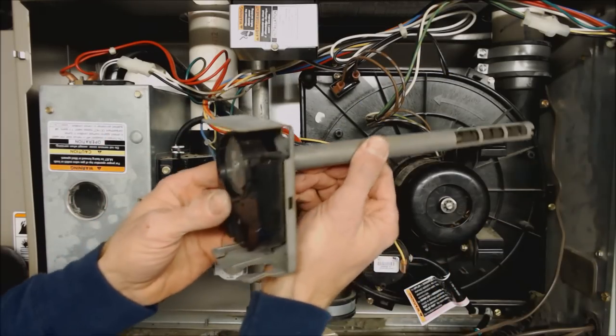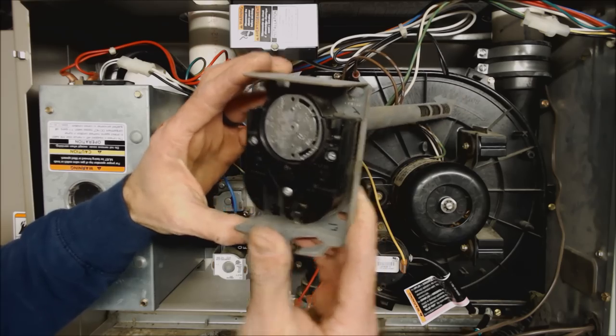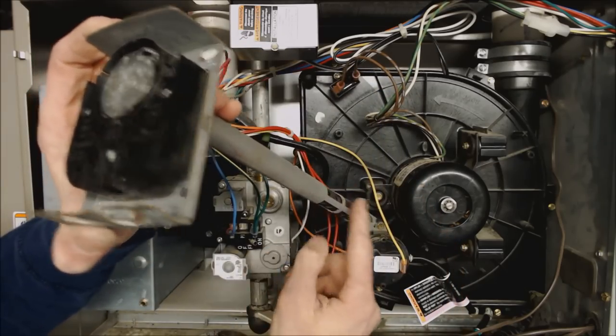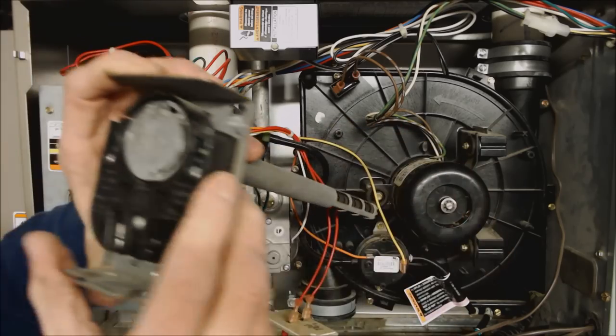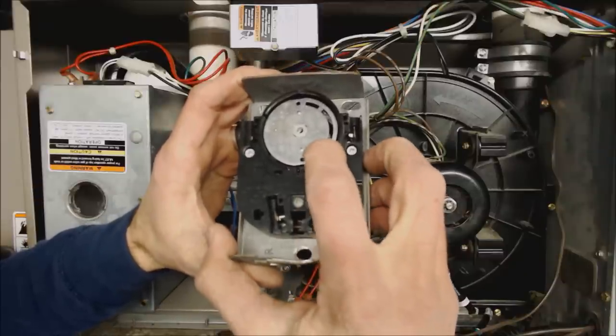Issue number two could be if you have an older furnace with a fan limit control such as this right here, you actually have three settings on this fan limit control. And this rod right here sticks into the heat exchanger and it has bimetal. And the bimetal, as it heats, it twists. So there's three settings right here. One, two, and three.